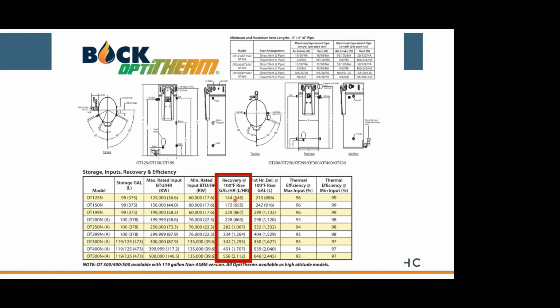But most of the time when you're doing sizing, you're looking at hourly recovery. As a result, you want your water heater to be based on hours of recovery, or how many gallons you can recover in that hour. All right. A typical design is 40 to 140, which happens to be a 100-degree delta T, or rise, increase in temperature. So most of the time you'll see manufacturers list their recovery with a 100-degree rise. So that's usually the chart you want to look at, or the column you want to look at if you're trying to match a load in a building.